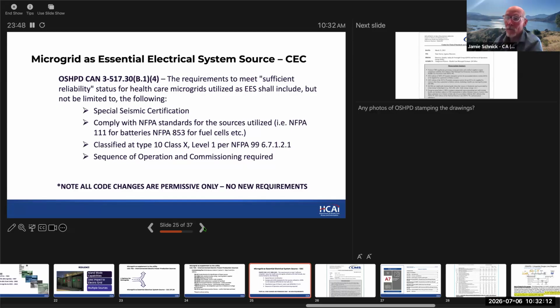NFPA 111 is written strictly for batteries as an essential electrical system, and NFPA 853 covers fuel cells. They need to be classified as Type 10, Class X, meaning they would start and assume the essential load within 10 seconds, with operating runtime specific to their class—for hospitals, typically 72 hours. We also require a sequence of operation and thorough commissioning under our observation, to confirm the system will operate as intended.